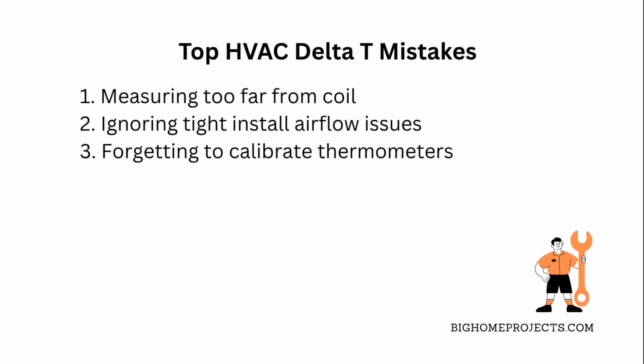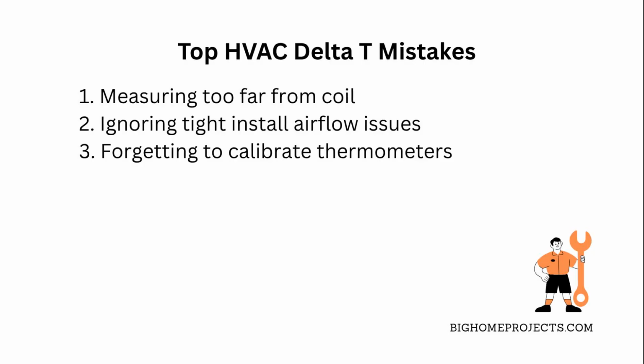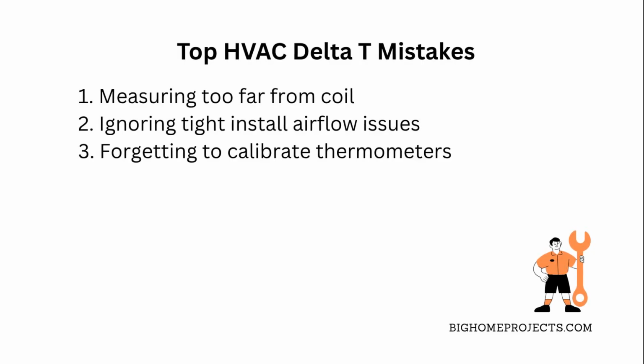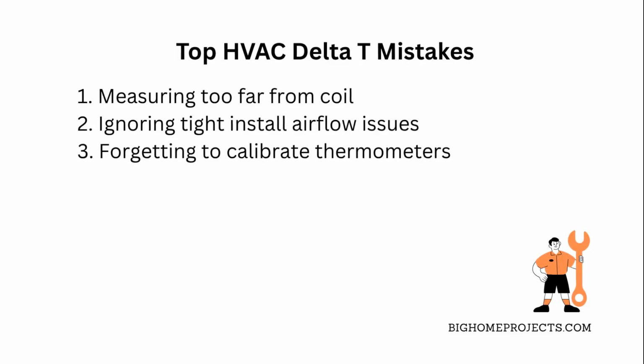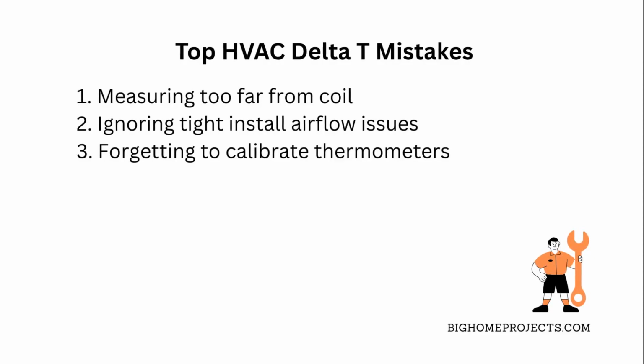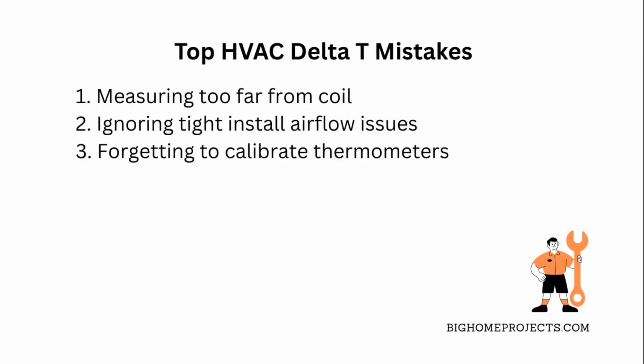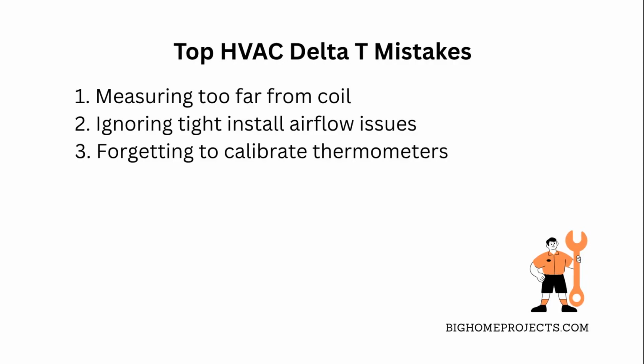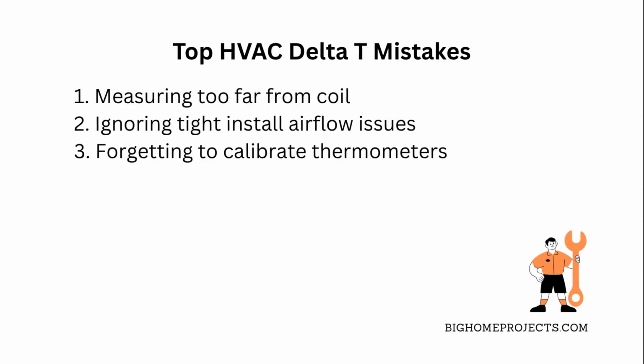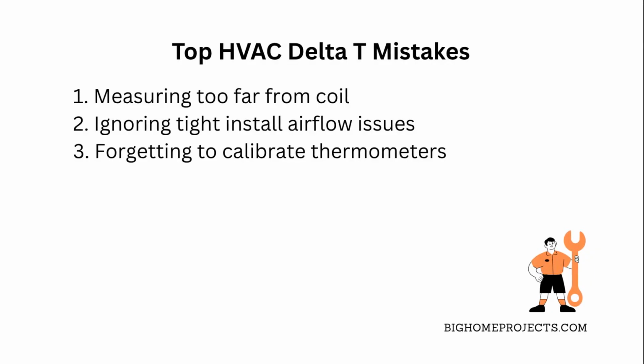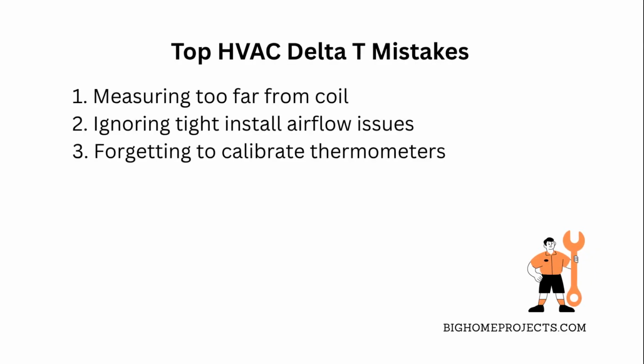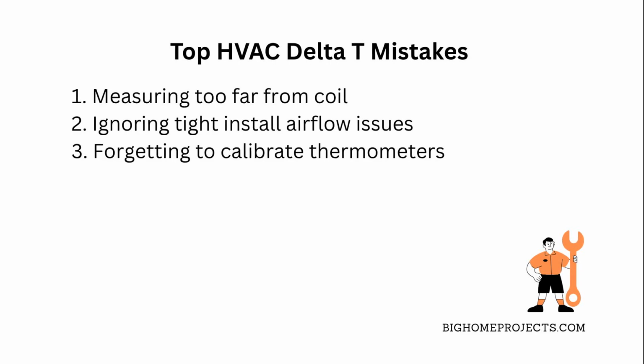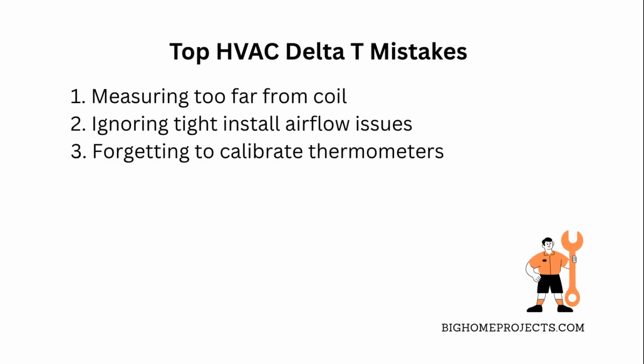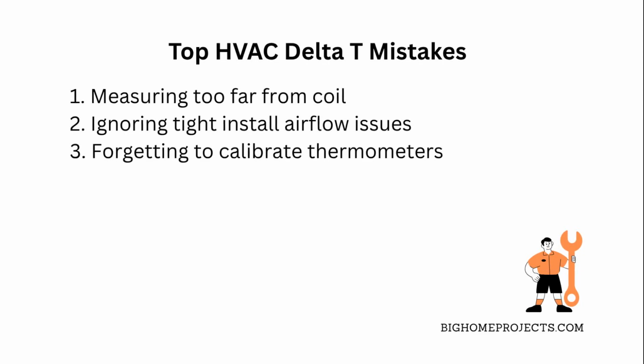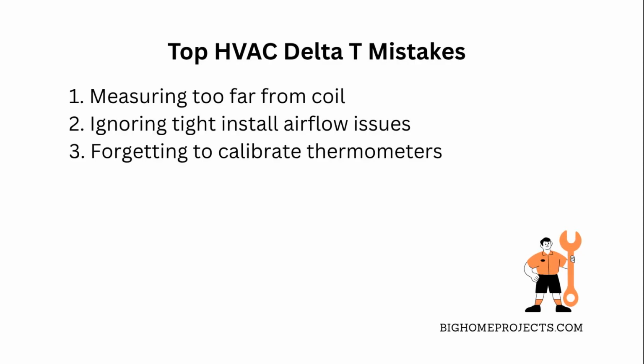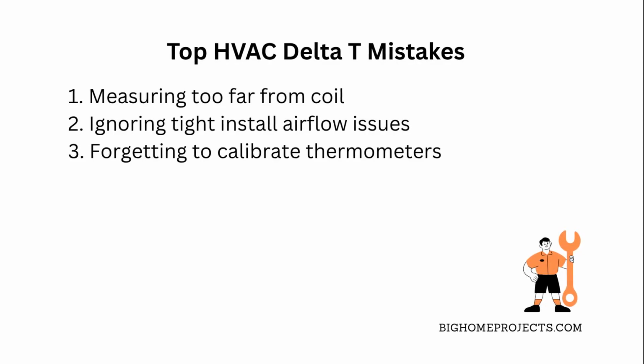One of the most common mistakes with HVAC Delta T readings is taking measurements too far from the coil or plenum, which throws off accuracy. Fix this by standardizing your measurement location right at the coil or plenum every time. Another issue is ignoring how tight installs restrict airflow, causing uneven temperature distribution. Using the right tools and positioning probes carefully solves this problem. Finally, people often forget to calibrate their thermometers, leading to faulty temperature data. So make sure you regularly check and adjust your instruments for precise readings.